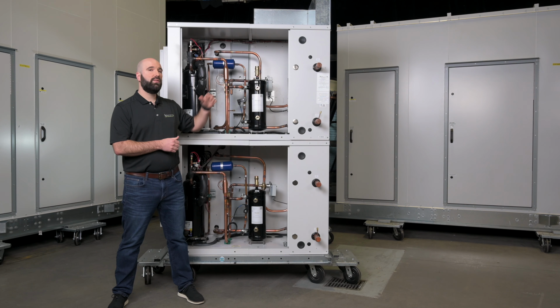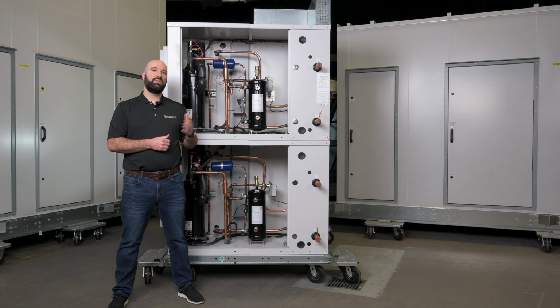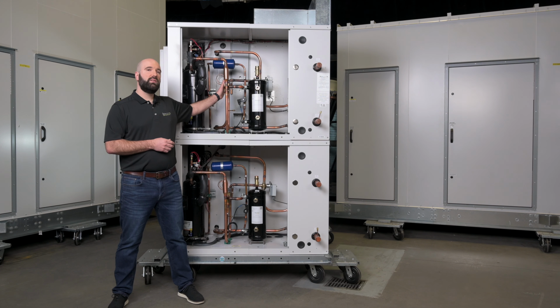Behind that, you've got a three-way modulating valve, and that modulates between the reheat coil and the air conditioning side, that flat plate heat exchanger, to change between air conditioning mode and dehumidification mode. Right behind that is an LAC valve, a low ambient control valve. That allows us to ensure that we're able to operate even down to a 0 degree Fahrenheit water loop, something that no other water-cooled equipment is capable of doing.